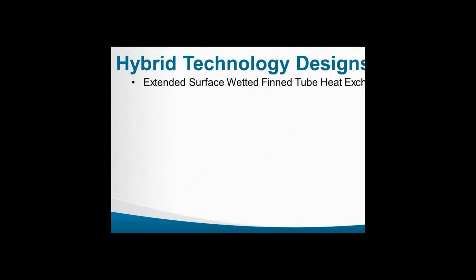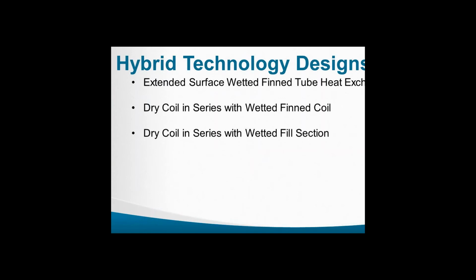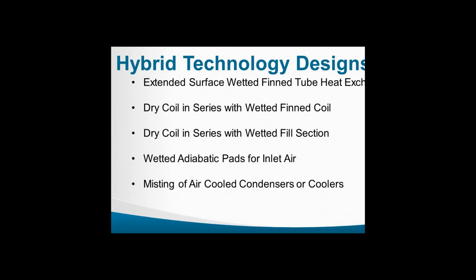You have extended surface wetted fin coils. You have these coils in series with an all-dry coil. Or you have a fill section with a dry coil. And this is popular in Europe, an adiabatic pad. It's like a wetted fill pack on the outside. And then you have a misting where you just spray water in front of a dry coil. And the last technology, for the power plants, is a wet-dry field-erected power plant cooling tower.